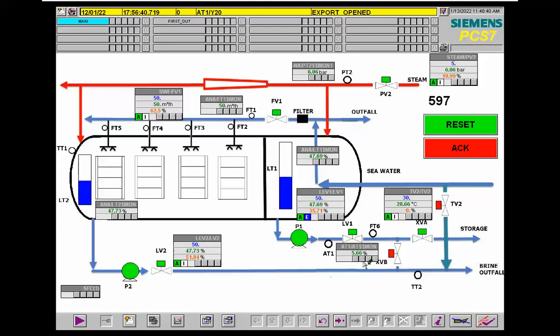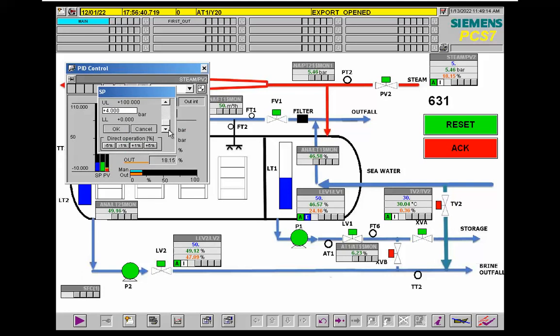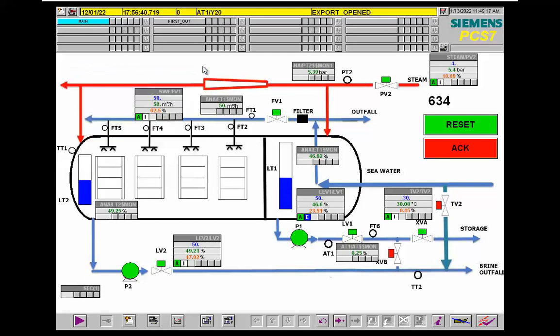The steam reduction has a bad effect on conductivity — the conductivity will increase, and these valves will change. The product will be transferred to the outfall; the product will be rejected when the conductivity is not suitable. I will decrease more. You can see that the product level is decreasing and the valve cannot maintain that condition.